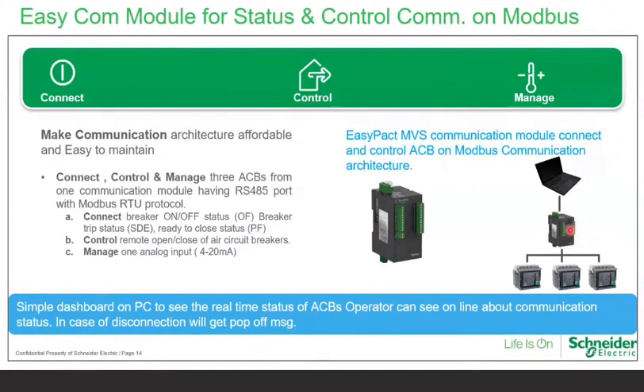We have 2 digital outputs for every breaker, which means we can remotely open and close the breaker. In addition to this remote status and control, we have an analog input inbuilt in this EasyCom module. It is by default a 4 to 20 milliampere input. You can connect a temperature sensor in the panel to the module, so that on communication or on the remote, you will get the panel temperature status also. So this is the EasyCom module.